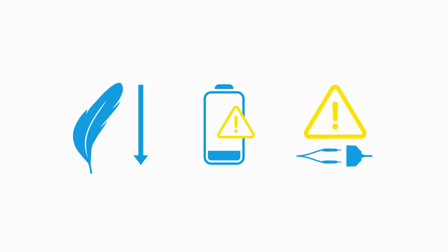This may be because the machine is oversensing, meaning the device is too sensitive and it's picking up a little noise and not putting out pacer spikes. Or it could be that the battery is low and you need to replace the battery. Or it may be that the lead is displaced or there's a loose connection.